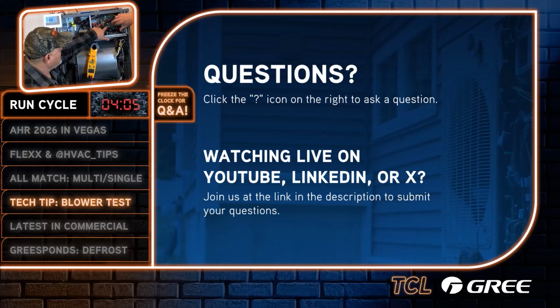He's got a question: if the fusible plug ruptures, does that mean the high pressure switch didn't do its job? I don't think so, not necessarily. It can indicate the fusible plug prematurely failed, but it's a bimetal mixture based on temperature. I forget the exact spec, I think it's in Celsius. It's not a hard rule of thumb, but if you've lost the fusible plug, chances are it just prematurely failed. It is a worst case scenario pressure relief device.